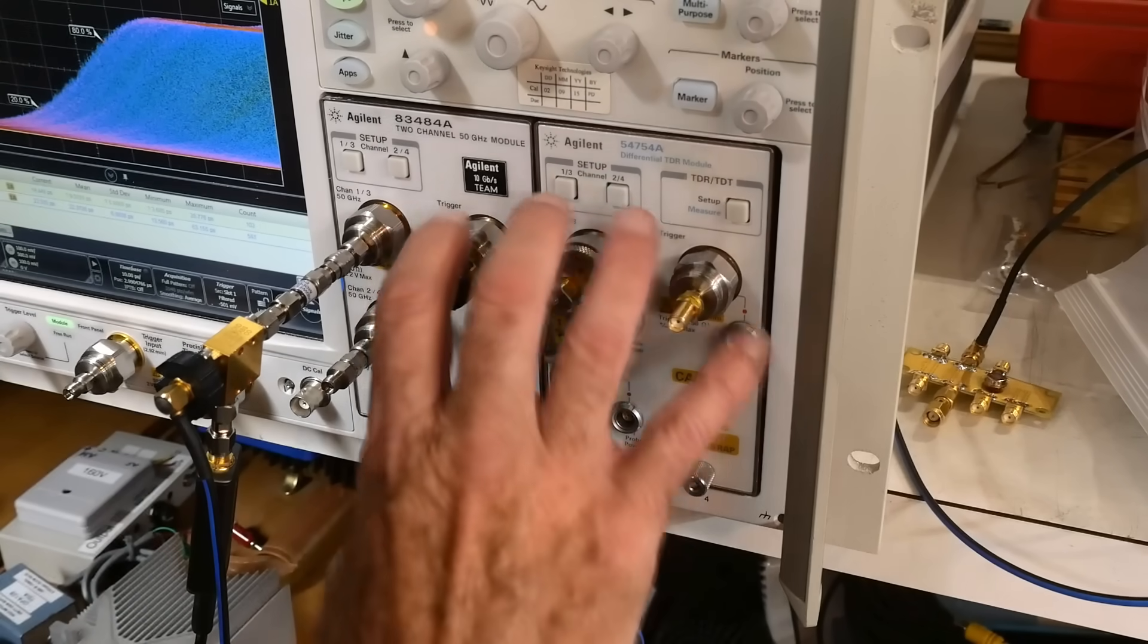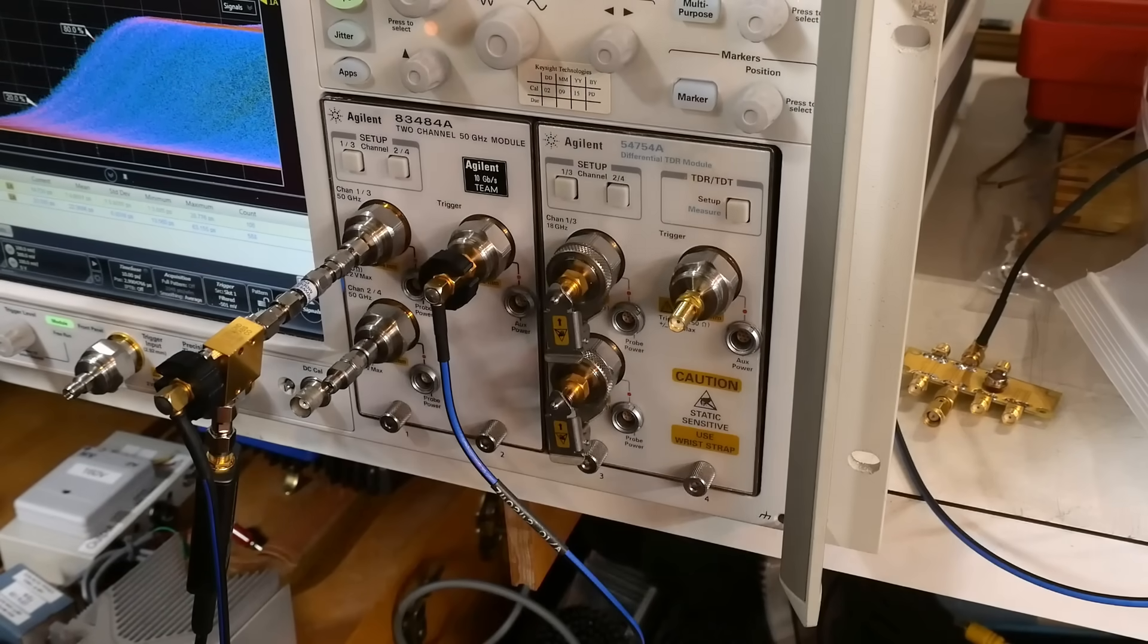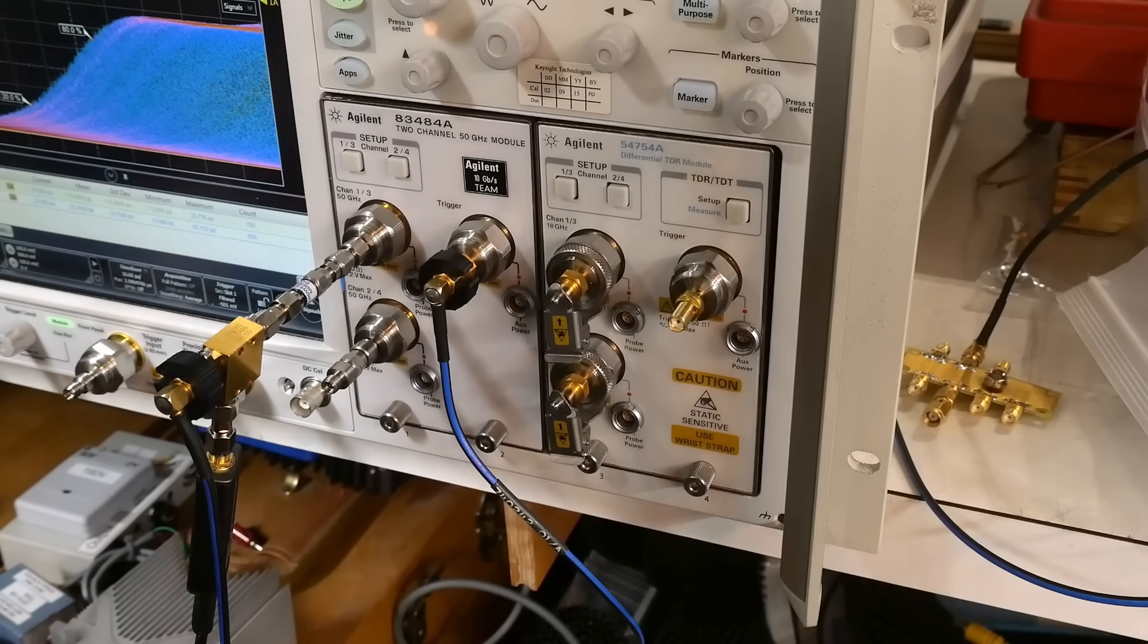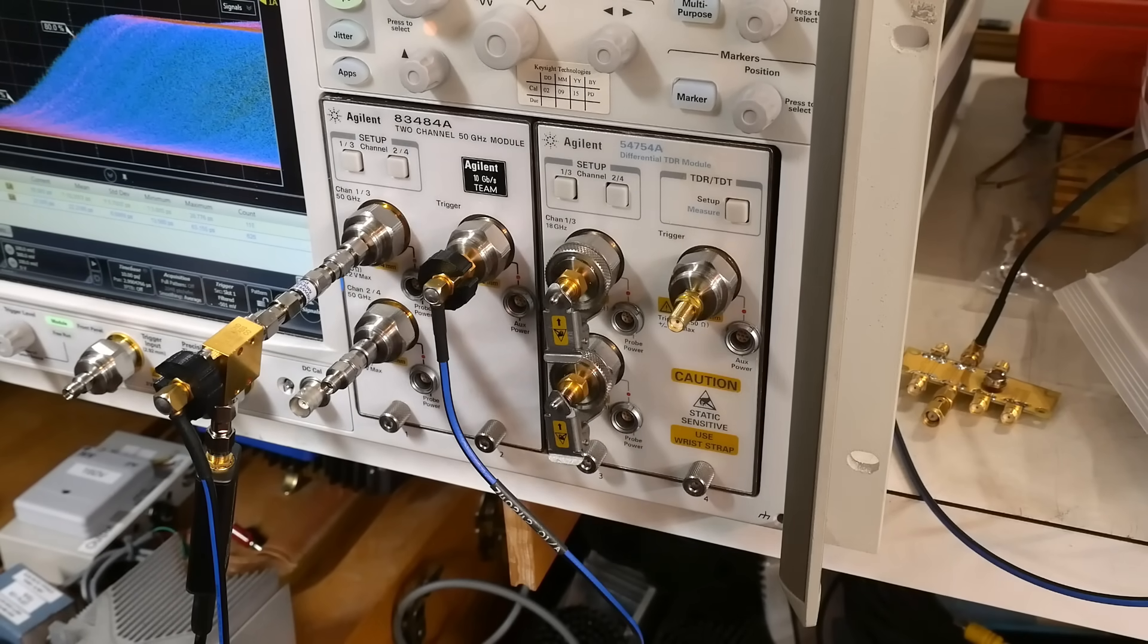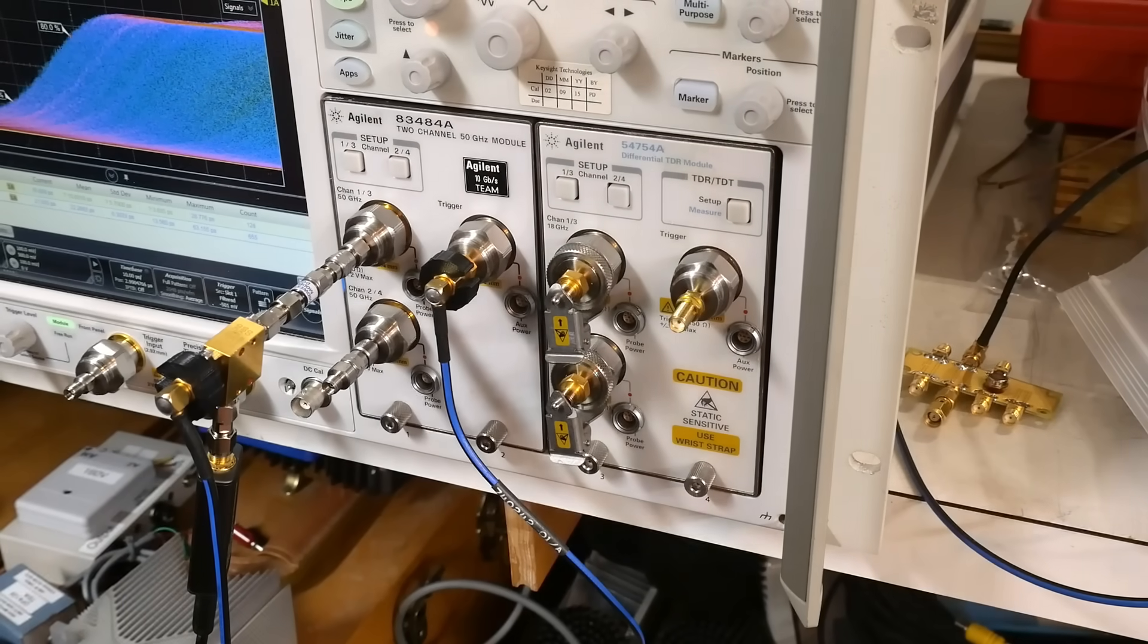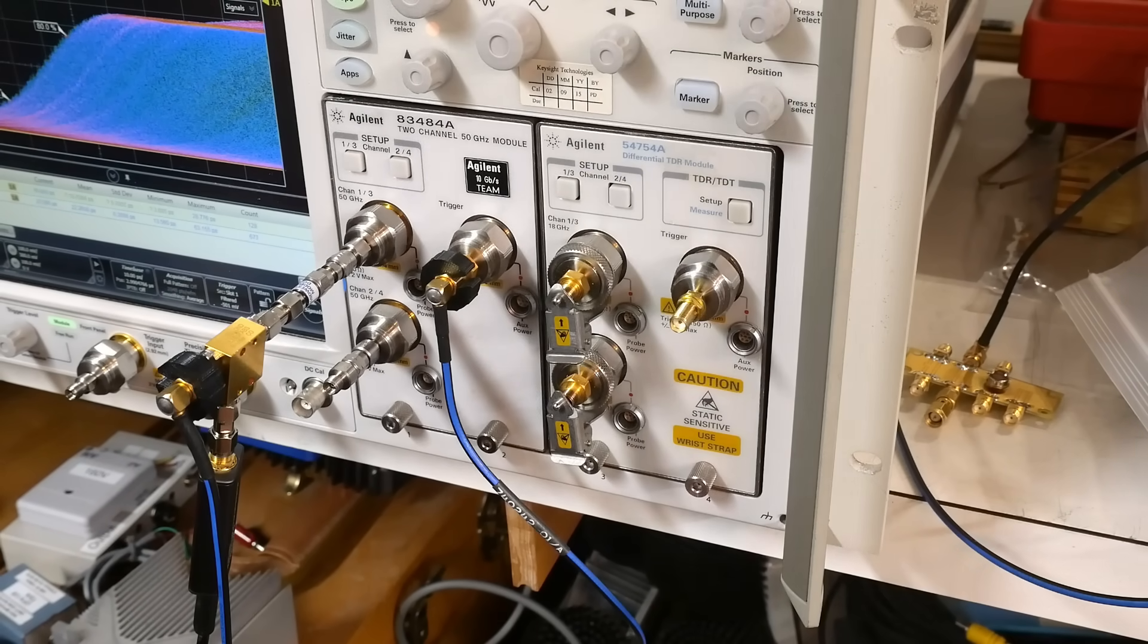So it's not an easy process on these types of oscilloscopes. You have to supply an external trigger. It does not have internal triggering, which means it can't trigger off the source.